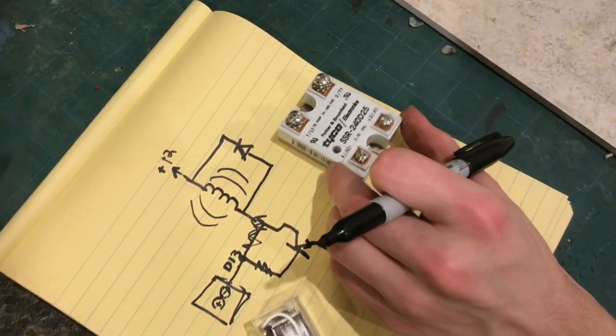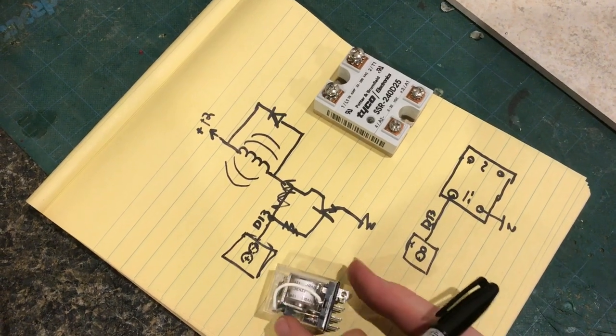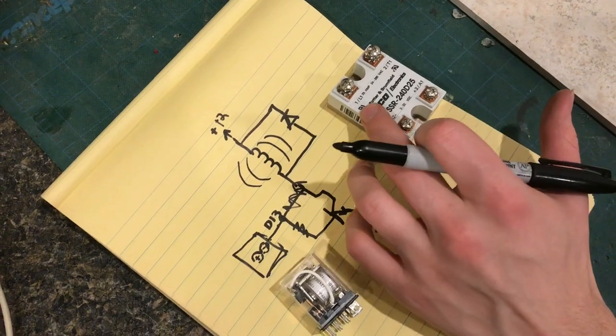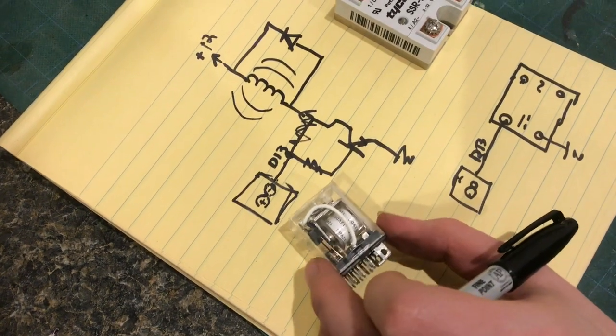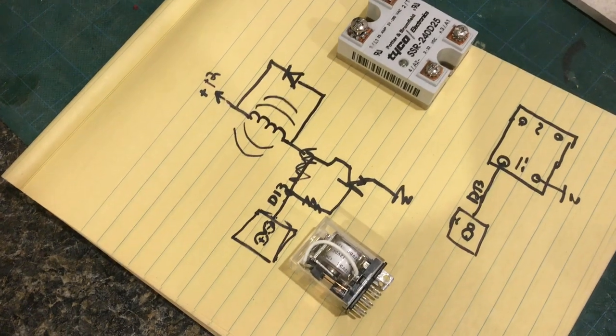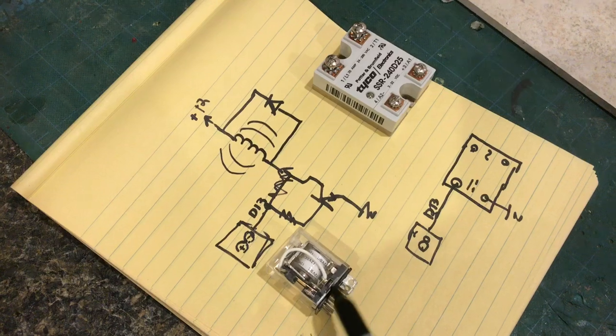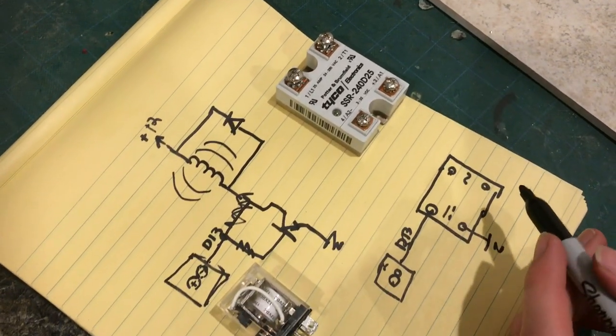Also these don't make the noise that a relay makes because there's no mechanical mechanism inside here. It also means you can turn this relay on and off much much faster than you can turn this relay on and off. One because there's a limit to how quickly this can move but two you'll wear out the mechanism by actuating it too rapidly. Whereas with this you know a thousand times per second you could turn it on and off perhaps and it won't care.